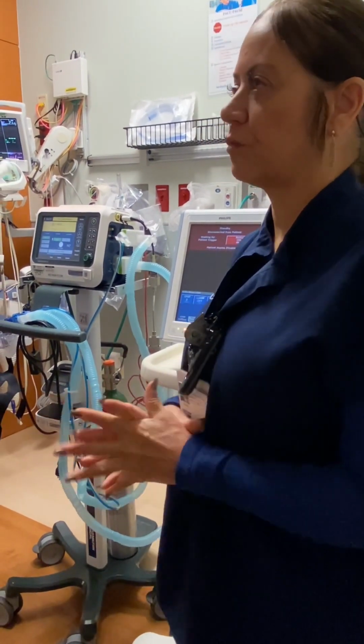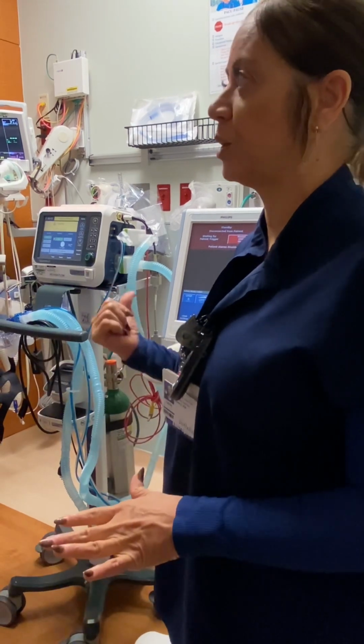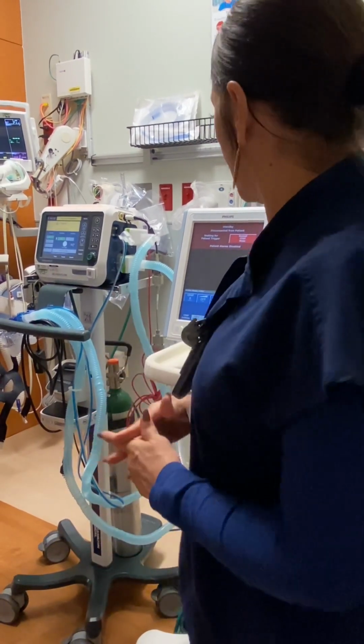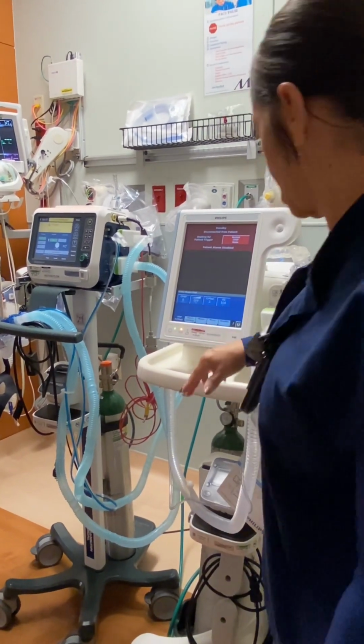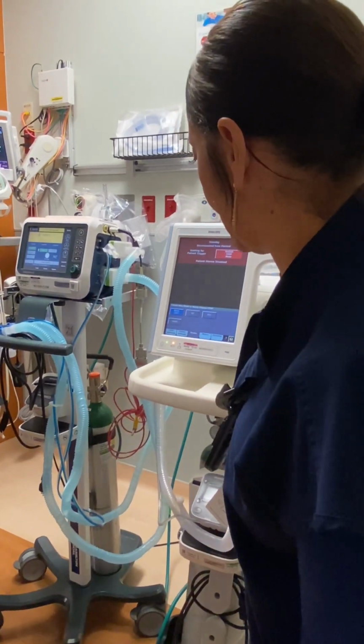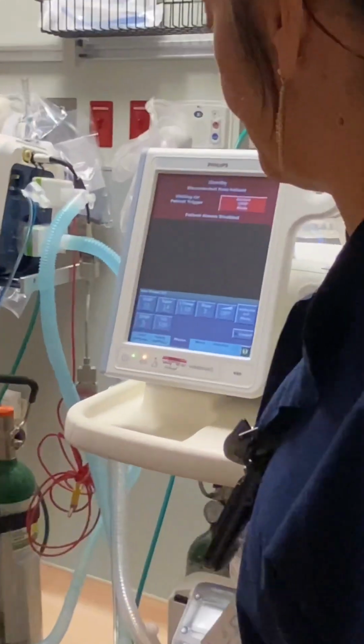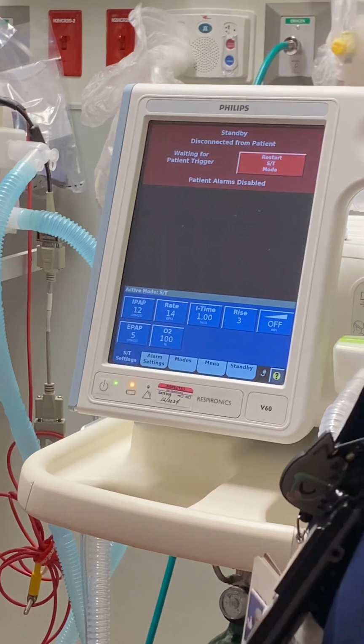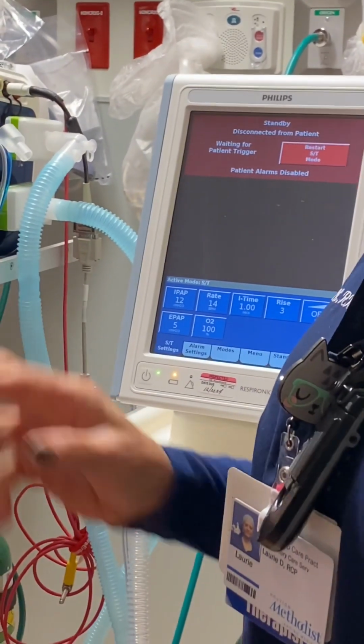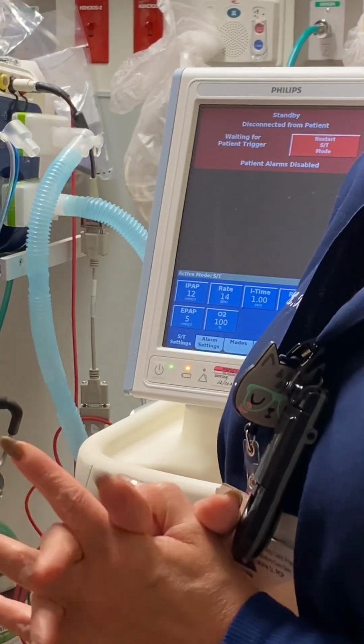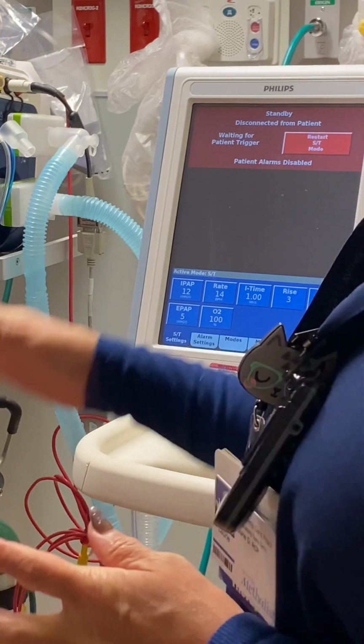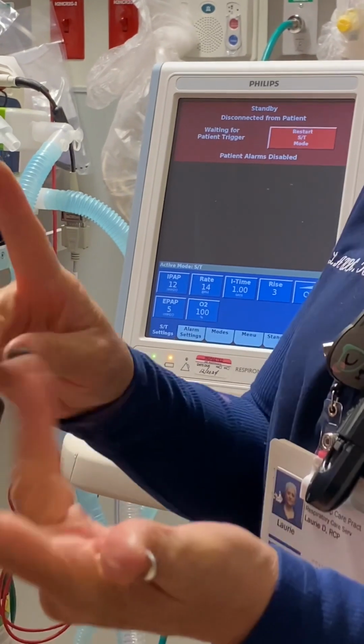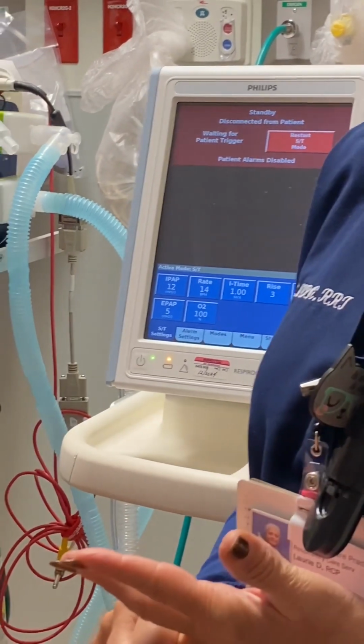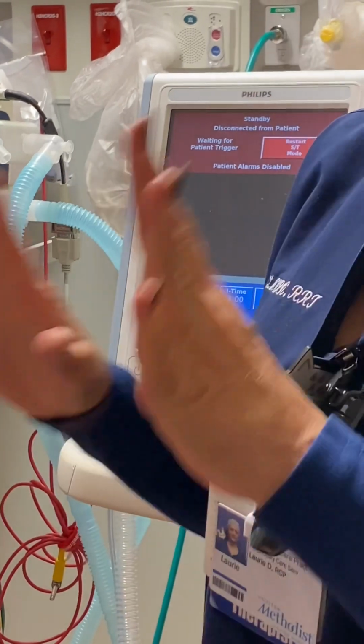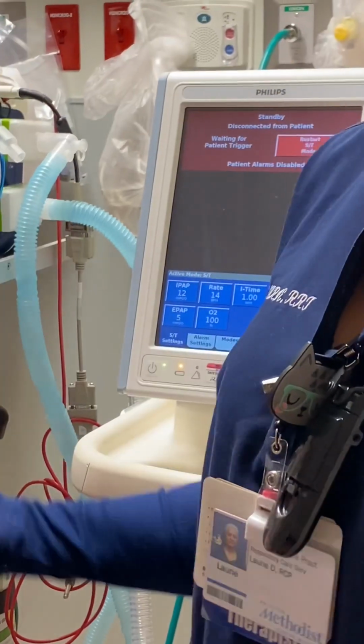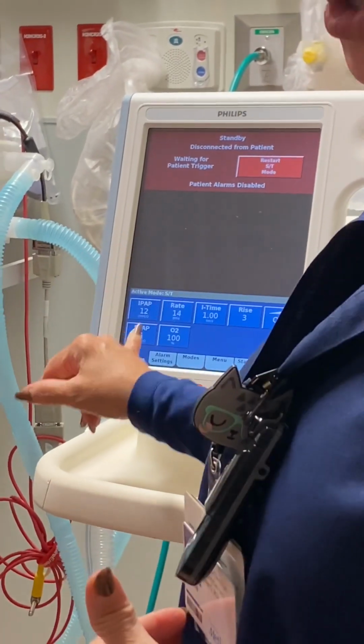Always call on the Vocera for respiratory lead if you have any questions after we apply this machine to them. Well, there's two settings, CPAP, and if you can also go to BiPAP also. That would be my ST mode here. Now, BiPAP is a little different. You know how you get the COPDers back here that have high CO2s and they're not waking up? This would be the mode for them. You can oxygenate and blow off CO2 at the same time. Where CPAP, you're not blowing off CO2, you're just oxygenating. This one would do both.